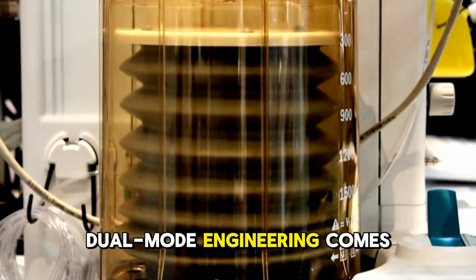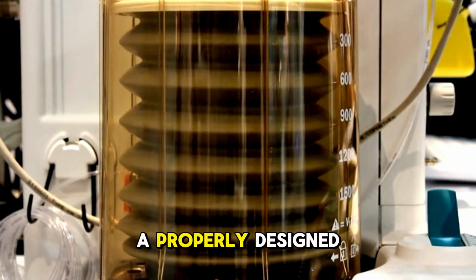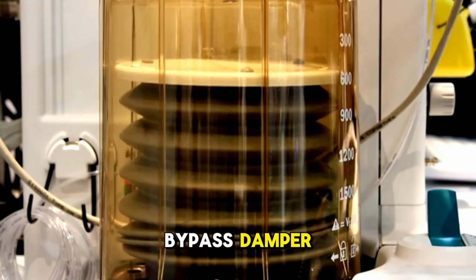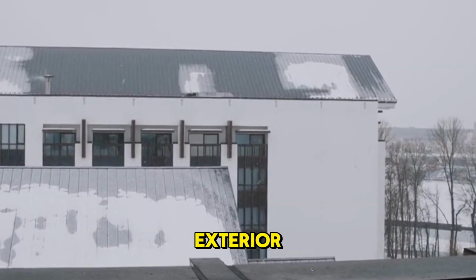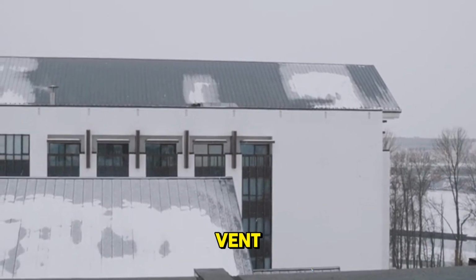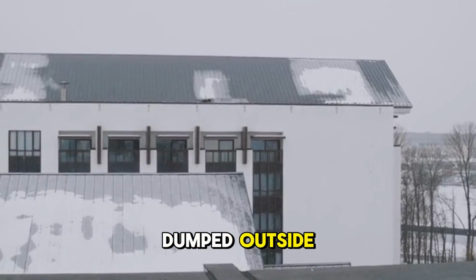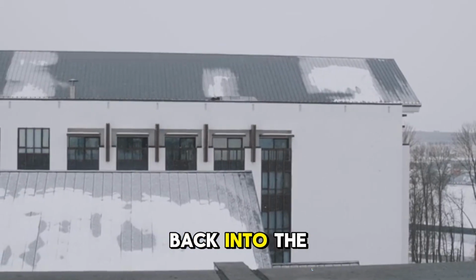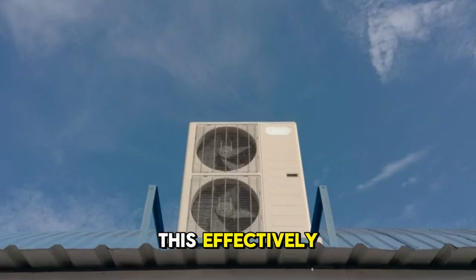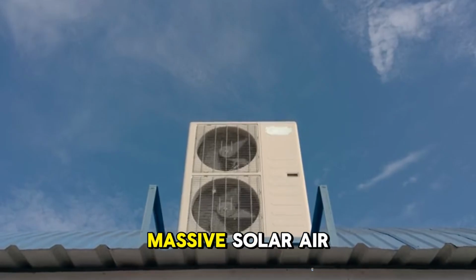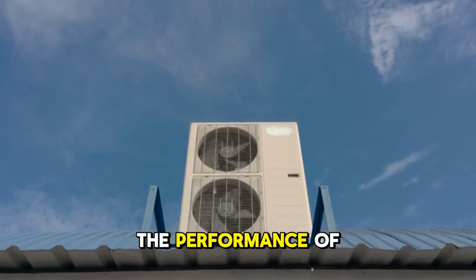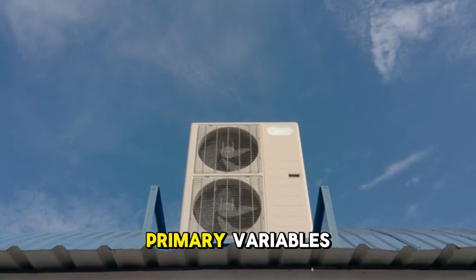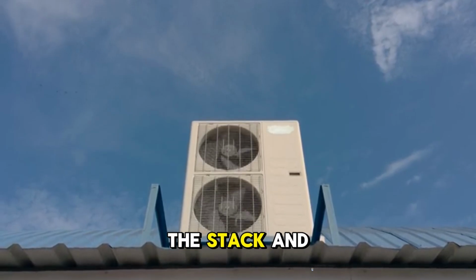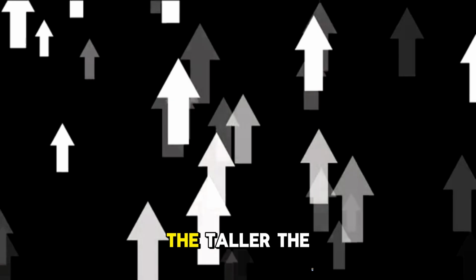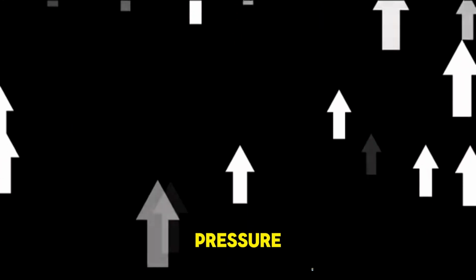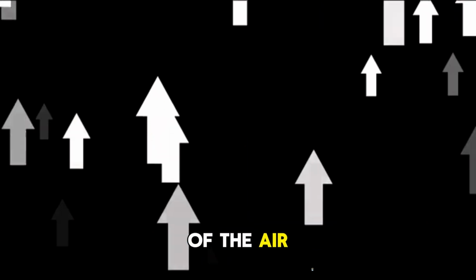This is where the dual-mode engineering comes in. A properly designed solar chimney includes a bypass damper. In the winter, you close the exterior exhaust and open an interior return vent. The rising hot air is no longer dumped outside. It is recirculated back into the building's thermal mass. This effectively turns your cooling tower into a massive solar air heater. The performance of this atmospheric engine is dictated by two primary variables: the height of the stack and the temperature difference. The taller the shaft, the greater the pressure differential and the higher the velocity of the air.